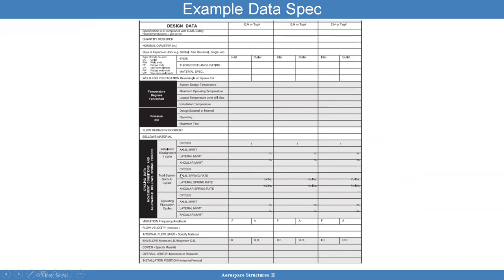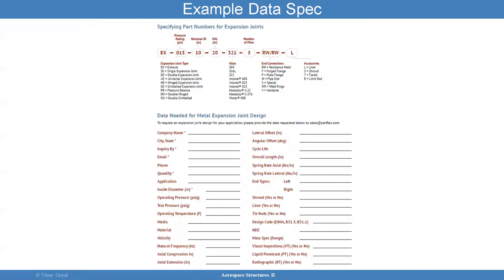Typically, when you design a bellows, you want to have a very nice spec that shows everything: cycles, lateral movements, spring rate, vibration, flow velocity, and so forth. Material used, number of convolutions, diameter, inner diameter, fluid media being used. It's like a checklist — very useful to look at what is the max pressure, mean pressure, temperature. All that stuff plays a big role in your assessment process. It's very important to have that spec sheet. Another example shows a different spec sheet. Some people want to show a lot of information with part numbers — EX could mean exhaust, with pressure rating, nominal diameter, 321 alloy, and number of convolutions.